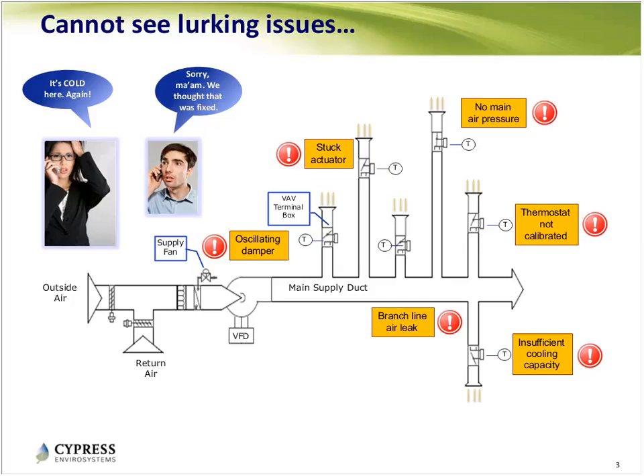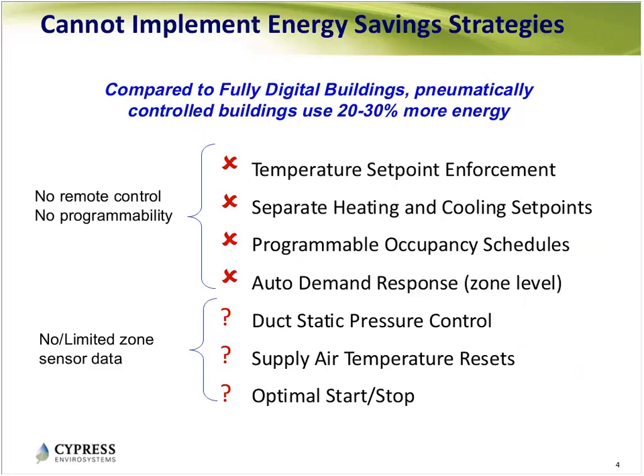Now let me dig into more detail about visibility. If you have a pneumatic system controlling your zones and thermostats with pneumatic actuators, one problem is you can't see a lot of things, and not just the thermostat. Your dampers may be stuck, you may have air leaks, or oil or water contaminating the pneumatic lines. You may have reset velocity controllers that aren't calibrated, so even though you think you're setting a certain temperature, it's actually controlling to another temperature. All of these are mechanical devices—they do not tell you if they have a problem. So it's not just the thermostat, it's everything around it that can go wrong, and you have very little visibility in a pneumatically controlled building to isolate and detect these faults.